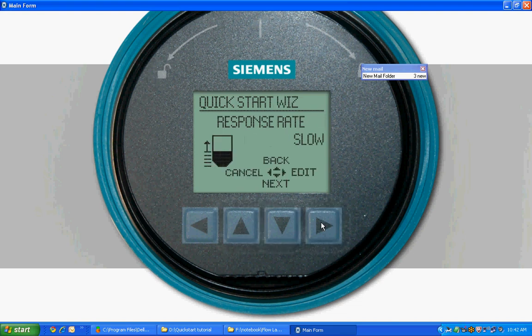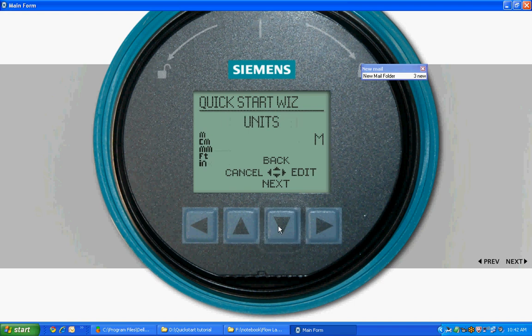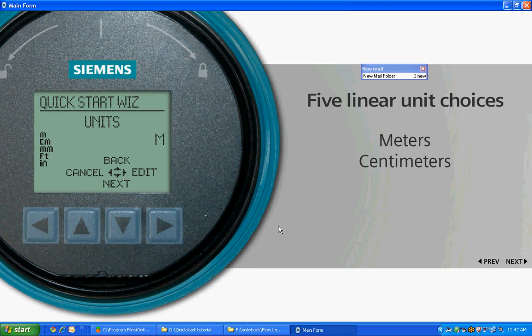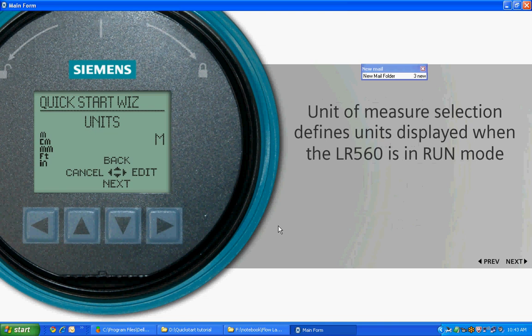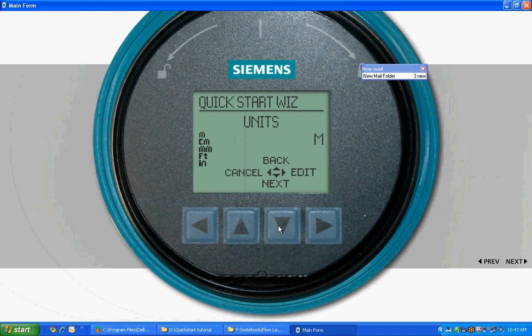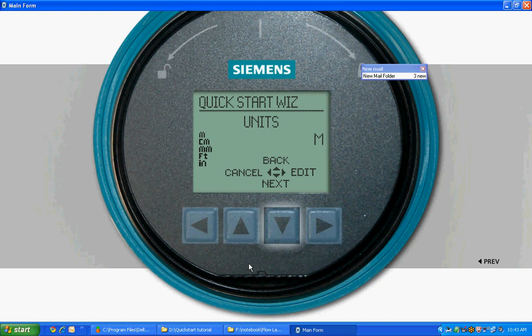There are five linear unit choices available: meters, centimeters, millimeters, feet, or inches. The unit of measure selection defines the units displayed when the LR560 is in run mode and the unit of measurement used for our high calibration point and low calibration point. Our application will use meters. Meters is the default parameter. Press Next to proceed to the operation parameter.